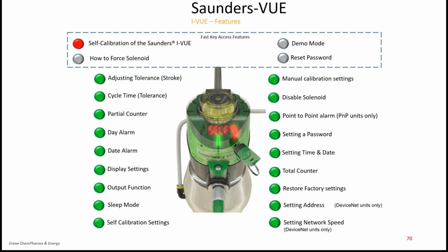Earlier, customers would not know how many times they have used that valve or how many cycles they have used on that actuator. But with I-VUE, as you can see, there's a screen on top that is the cycle counter. So it counts every time the valve is opened and closed. Customers or the end users in pharma can use this to modify their maintenance cycles and change the diaphragm only when it is required. Whereas today, customers just follow a set maintenance schedule and throw away the diaphragm even if it is good. So having sensors like this on diaphragm valves gives customers the power to change their preventive maintenance schedules and optimize their maintenance cycles to get the most out of the diaphragm which is in there.